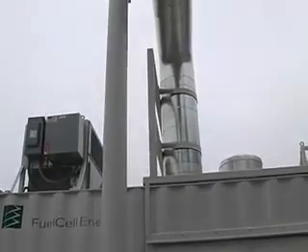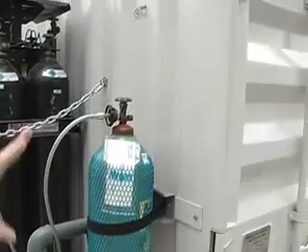We'll talk about our heat recovery side. You'll see up here the exhaust leaving one of the units. We combine all four exhaust flows from each 250 kilowatt fuel cell unit, and then a fan pulls that exhaust up to the roof where it goes to our two heat exchangers. We're taking the 700-degree air and bringing it down to about 190 degrees, feeding that heating hot water — coming out at about 250 degrees — into our heating hot water loop. When the second part of the project is complete, we'll be providing heating hot water for the swimming pool across the street and the Student Union's domestic hot water. This is also where the fuel is fed into the system from the gas company, pushed into the fuel cell stack where the reforming takes place and it's converted into hydrogen.